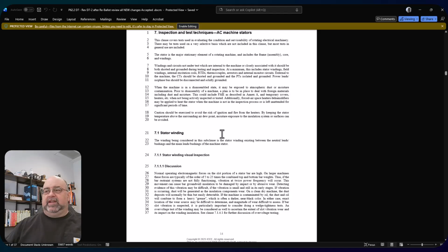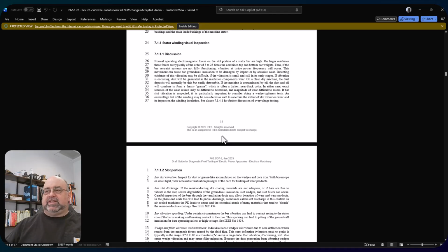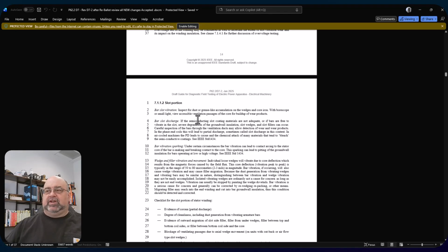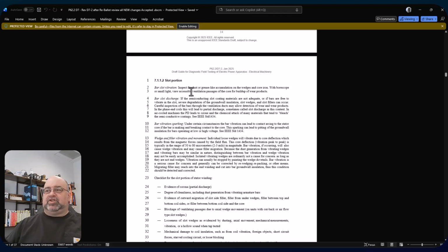So, stator winding visual inspection—let's take a look at this slot portion. Bar slot vibration, look for dust or grease, bar slot discharge. If bars are free to vibrate in the slots, there's severe degradation of the ground wall insulation, and it will of course reference you to the appropriate standards, such as in this case partial discharge, where ozone attacks the material.